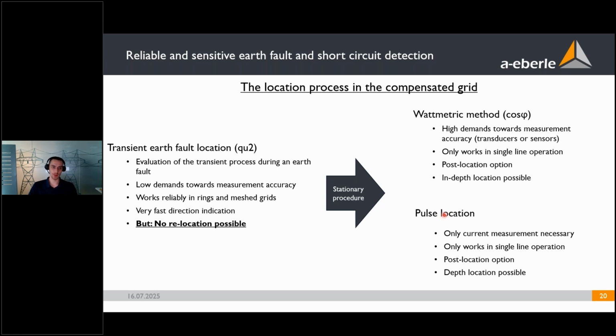Here you see a typical location process in a compensated grid, but this would also work in an isolated grid. The only difference would be that your stationary procedure would use different localization methods, but in general, the same two steps. So at first you have the transient earth fault location with our QU2 algorithm. And this algorithm evaluates the transient process during an earth fault.